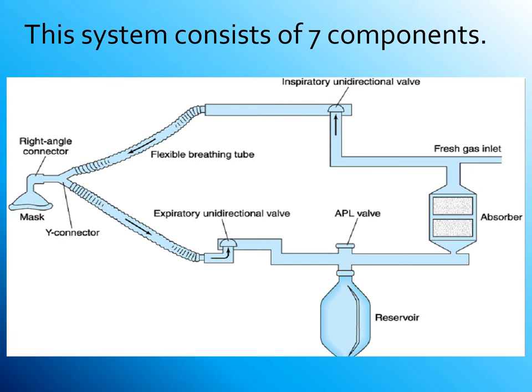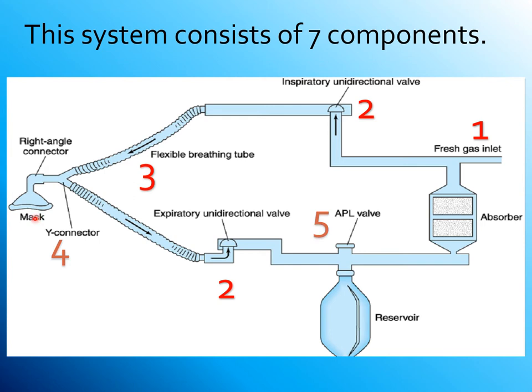The components of the circle system are: first, the fresh gas inlet; second, the inspiratory unidirectional valve and the expiratory unidirectional valve; third, flexible corrugated breathing tubes; fourth, the Y-connector which connects both tubes to the patient; fifth, the airway pressure relief valve or expiratory valve; and of course the reservoir bag, and the absorber or canister that contains the soda lime.